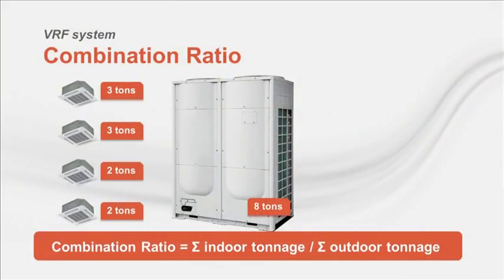In our example, the total combined capacity of the indoor units is 10 tons, and it is connected to an 8-ton outdoor unit, which is a 125% combination ratio. But use caution. Designing in excess of the manufacturer's combination ratio may risk comfort problems on days with extreme temperatures combined with peak heating or cooling loads. The flexibility of VRF systems presents lots of design options, but there are some practical limits to just how big a system can be. One of these limitations is refrigerant piping.